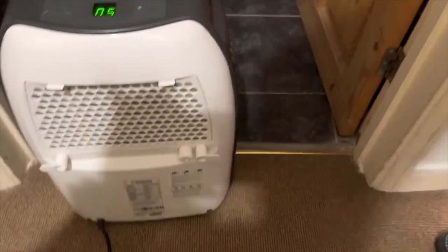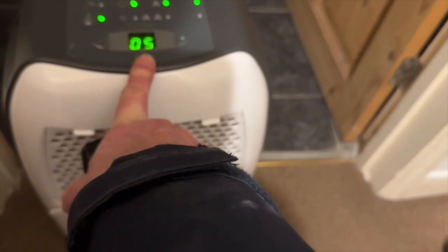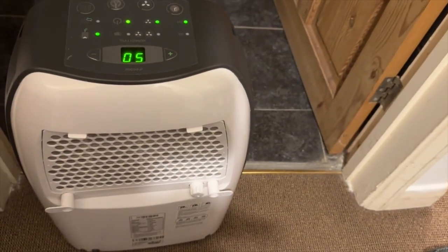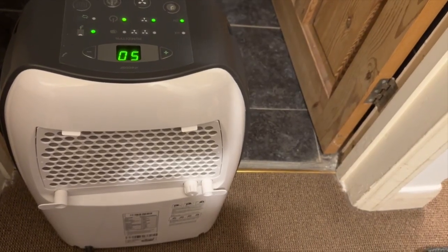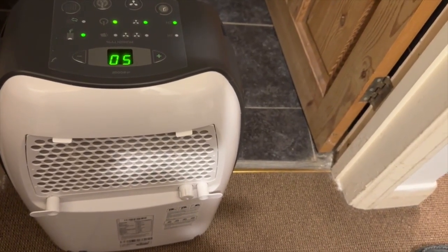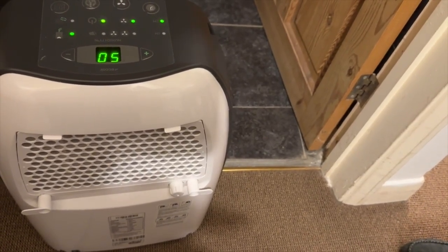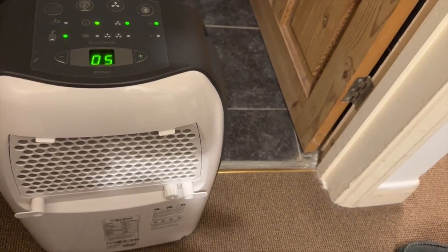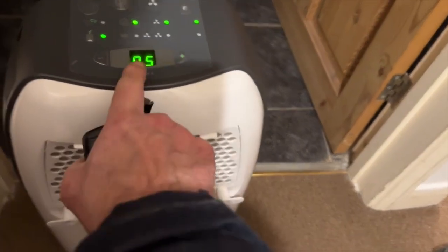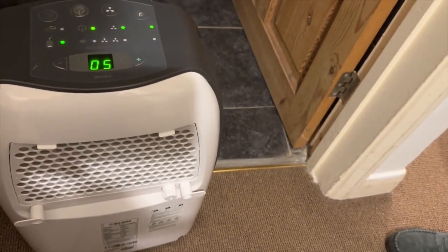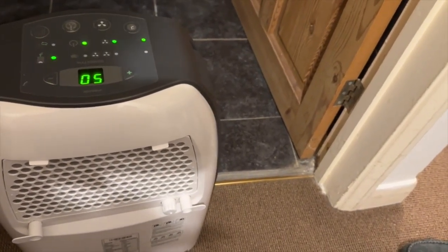Yeah. That 50% is, A, not necessarily that accurate, and B, it's in a central location which is much warmer, and that could be 20 degrees centigrade, but the wall could be 10 degrees centigrade, and so roughly speaking, every 1 degree centigrade increases relative humidity by 5%. So that 10 degrees centigrade change will move it from 50% here to 100% on the wall. So you've got to take into account that element.